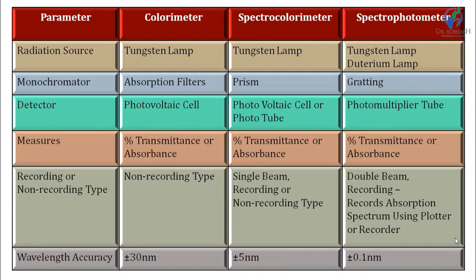Bandwidth affects accuracy. In colorimeter, bandwidth is ±30 nm. In spectro-colorimeter, it is ±5 nm. In spectrophotometer, it is ±0.1 nm. For example, ±30 nm means if lambda max of a compound is 500 nm, radiation of wavelengths from 470 nm to 530 nm will be obtained. That range is known as bandwidth.